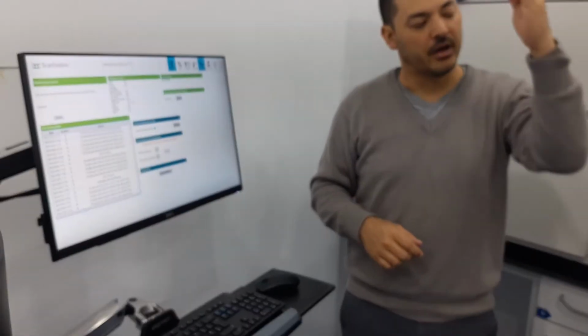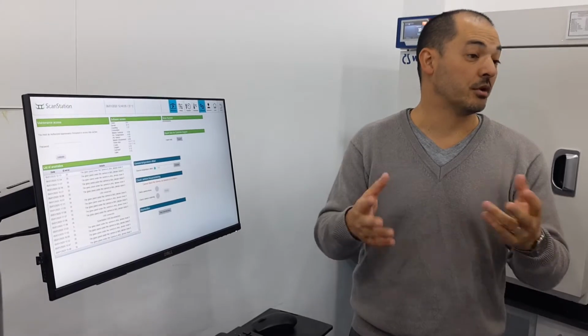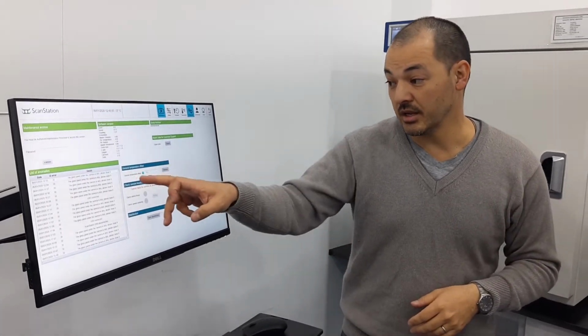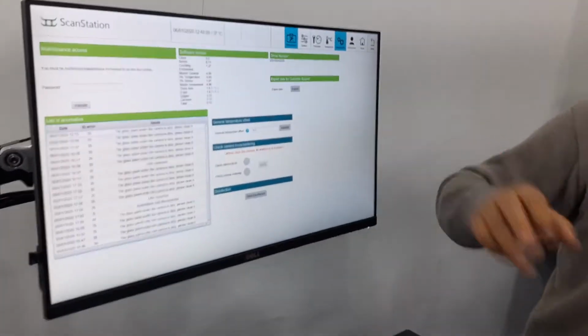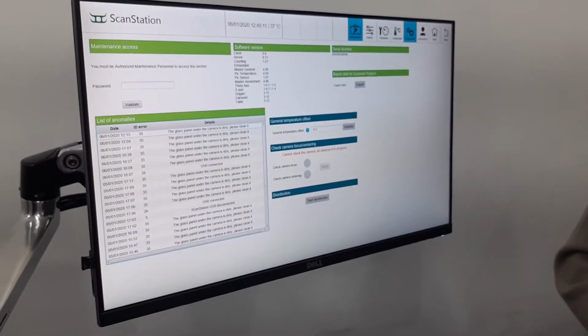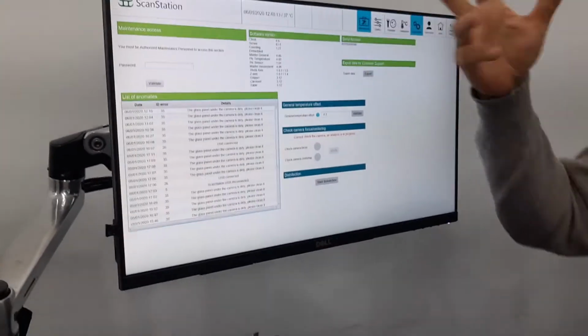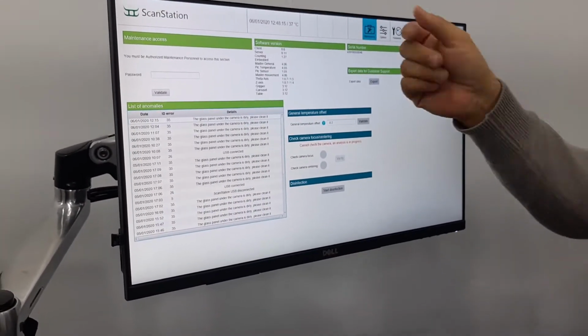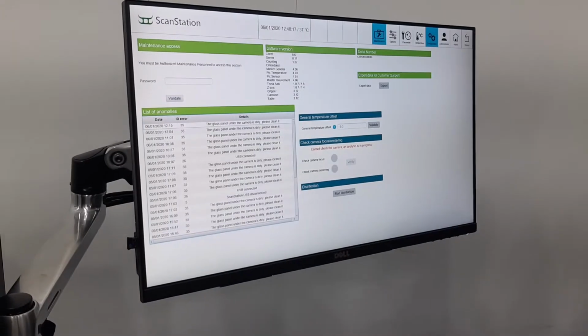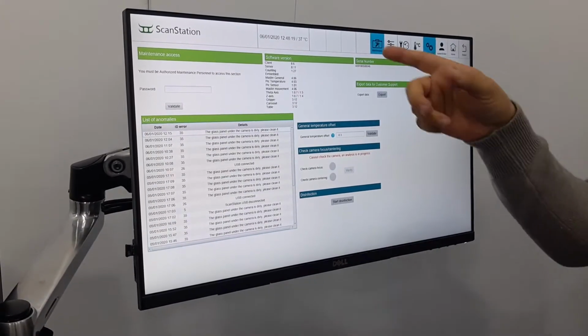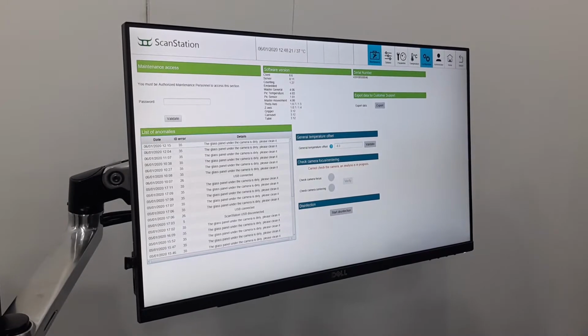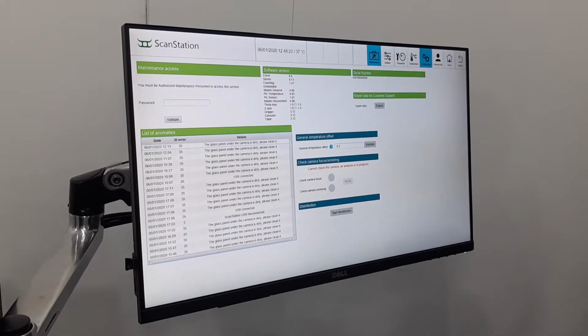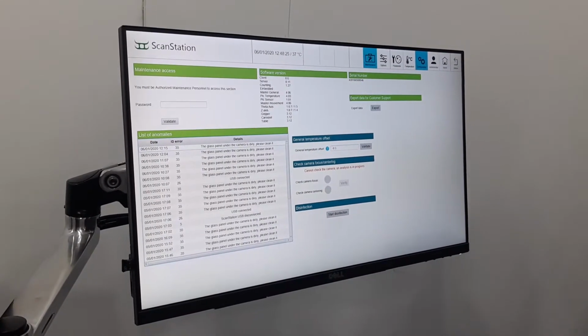Because maybe the sensor drifts a little bit, so it's sensing a little bit too high or a little bit too low after a few years. So you can change the offset of the temperature so that the indication is good. Otherwise, you can put a post-it, add 0.2 degrees, but it doesn't look nice, so it's better to offset. Here it's minus 0.3, so that's the calibration we did at the factory.